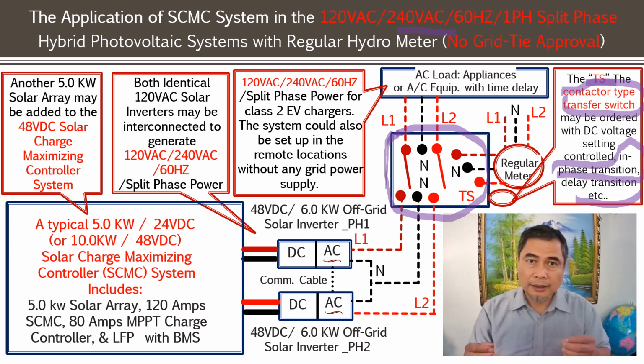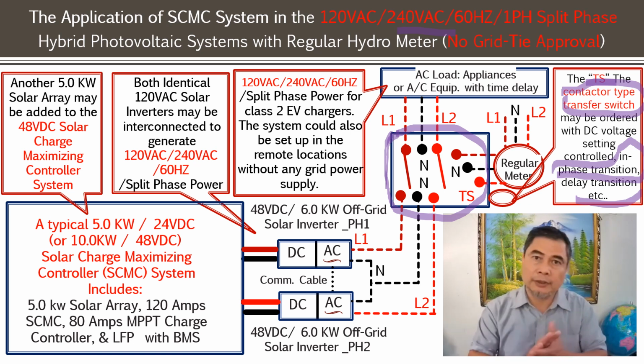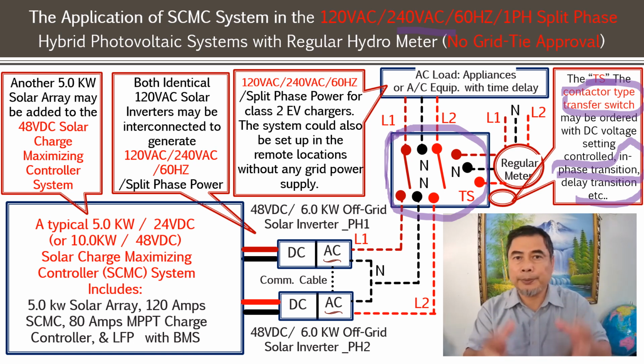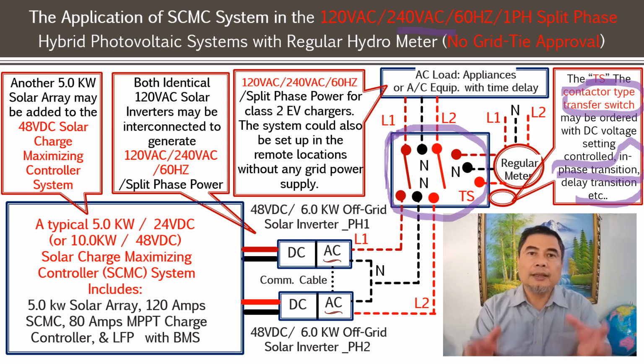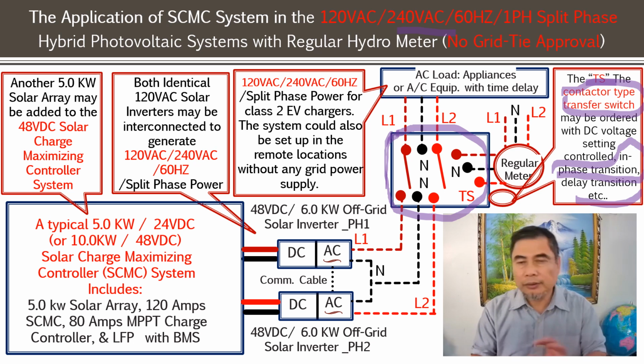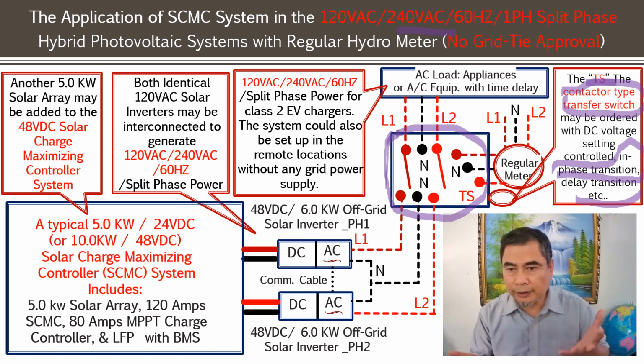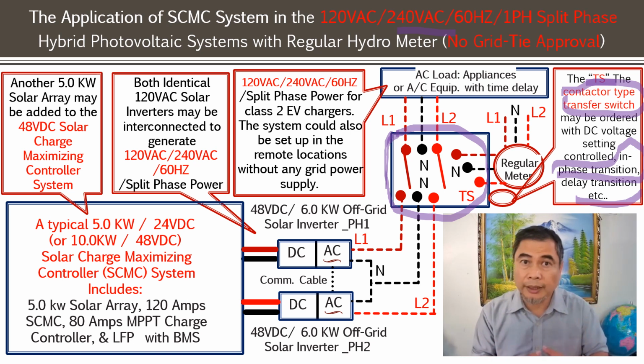And then if the power suddenly goes off and the compressor stops, if it wants to start right away, the compressor will hit a significant resistance because high pressure has already built up in the system. But if the equipment has some kind of protection built in, you would have no problem. You don't need the delay transition if that's already built in. But for some motor equipment, you do need to make sure it's in phase. This transition is also built into the transfer switch.